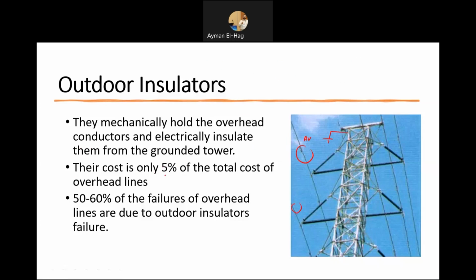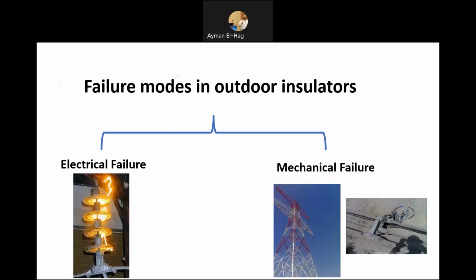Now, the cost of those outdoor insulators is only 5% of the total cost of the overhead lines. However, 50 to 60% of the failures that happen on overhead lines are caused by outdoor insulator failures. Now, you can classify the failure of outdoor insulators broadly into two main classes. Electrical failure, when a flashover happens on the insulator surface, which will lead to a line to ground fault, which might trip your protection system, or mechanical failure that can happen as well.